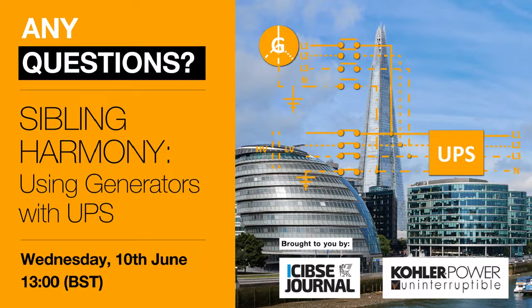Okay, that leads us very nicely into a question from Robert here. Perhaps you could just explain, and I think someone's been doing their homework here, what is an SCR after treatment system? Yeah, it's an exhaust after treatment system that uses an urea injection that is used on newer equipment and on older equipment. If you've already got a generator installed somewhere that you don't want to remove, but you want to improve its emission level, there is a system available through UPSL, an SCR system that can be retrofitted to older generators to clean the gases coming out of the NOx levels by reducing them and bringing it within tolerance of latest legislation, or as close to. So the SCR system is an after-treatment cleaning system that is available. Okay, and I think that stands for Selective Catalytic Reduction as well, for those who are not familiar with that acronym.